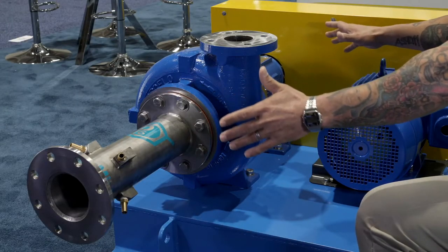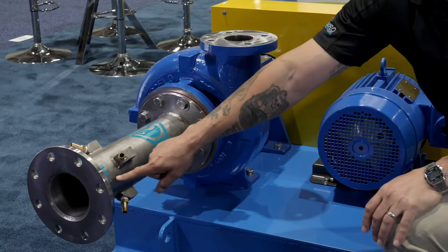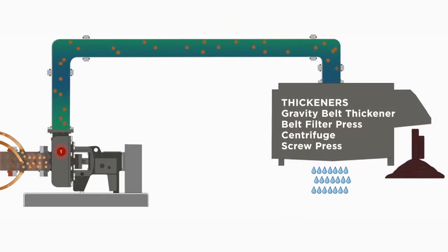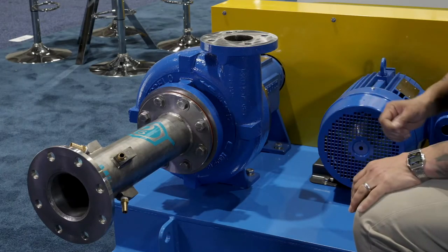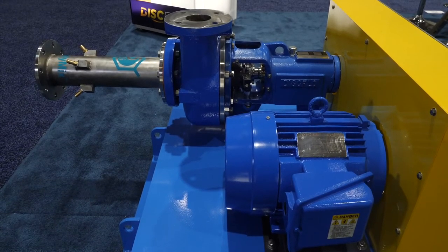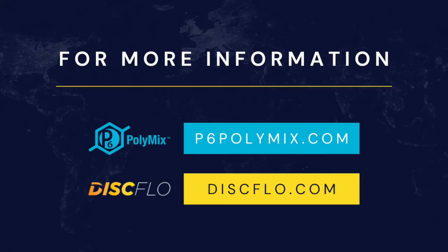We make the P6 PolyMix system in multiple configurations: close-coupled, belt drive, and direct drive. You'll always have the inject chamber on the front end of your pump feeding the polymer in. We're agnostic to your polymer system or dewatering system — we'll work with anyone's polymer makeup system and feed anyone's dewatering equipment, whether it's a screw press, belt press, gravity belt thickener, rotary thickener, or clarifier. We typically have a double cartridge seal on our pumps, which allows you to run the pump dry without damage. We use IEEE 841 chemical processing motors. For more information, visit p6polymix.com and discflo.com.